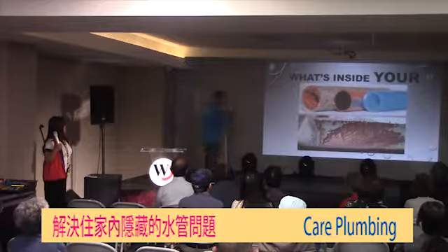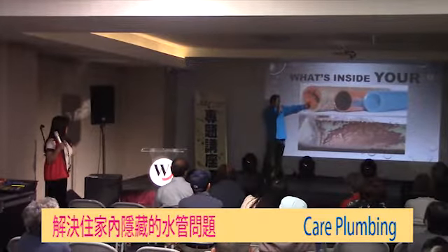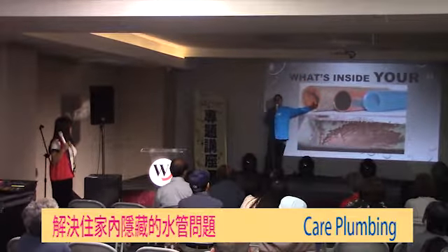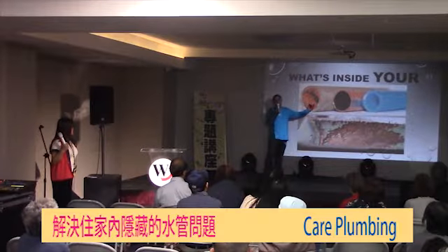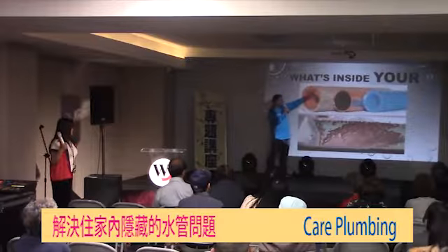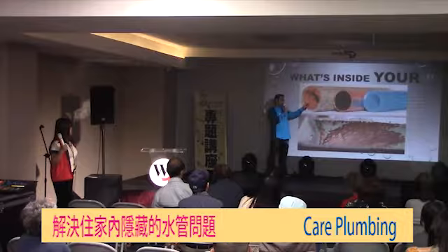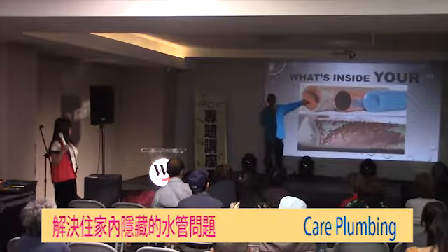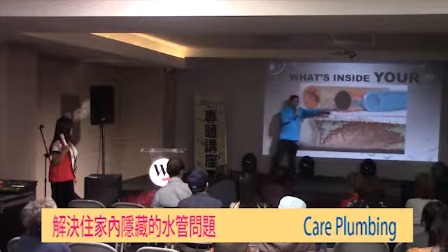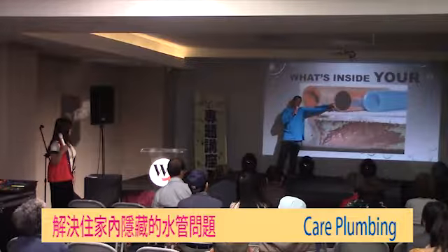In this picture, you can see this is the galvanized pipe, and from outside it's silver color. When the pipe is new, it's the same color inside. You have that zinc coating, but after some time it wears out, and then you get oxidation, a rust, corrosion buildup inside the pipe. This pipe you don't use anymore for water purposes. What we use is copper, or the last one, the blue pipe, that's PEX.